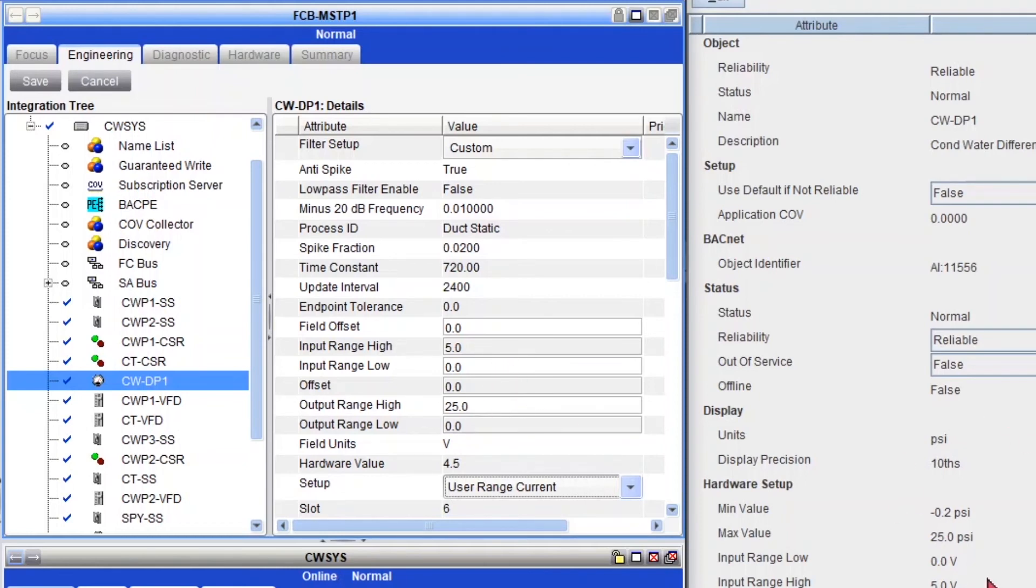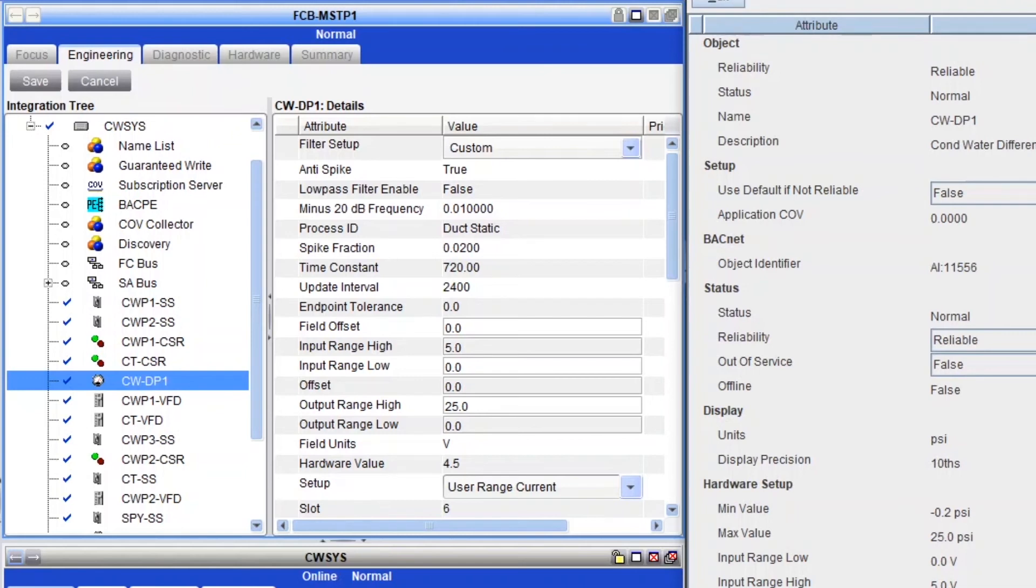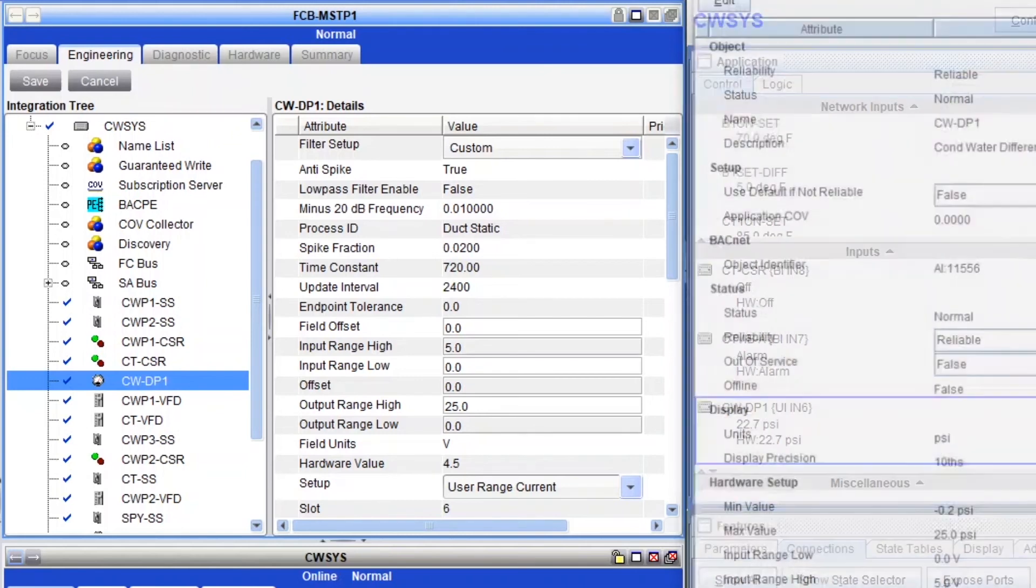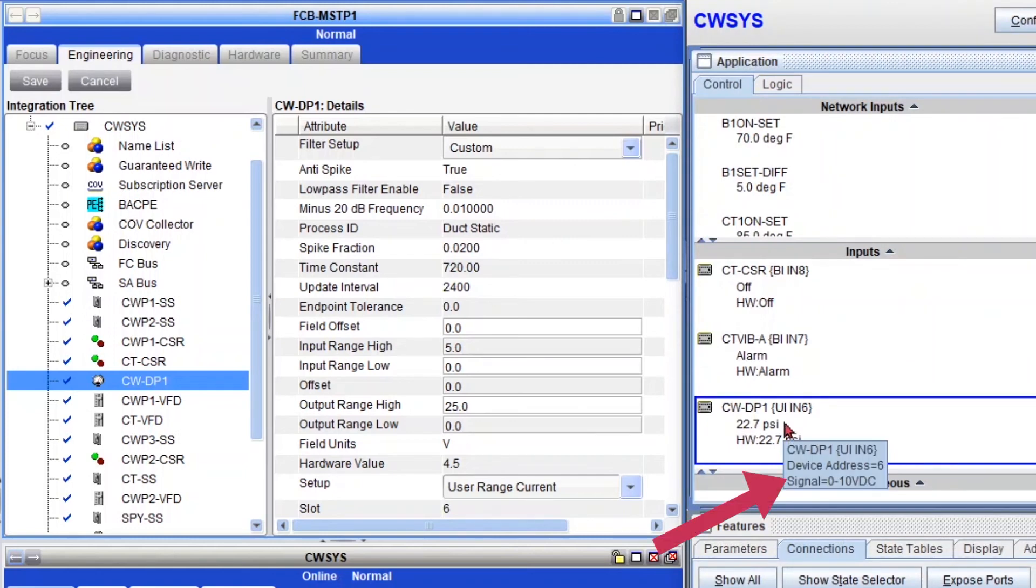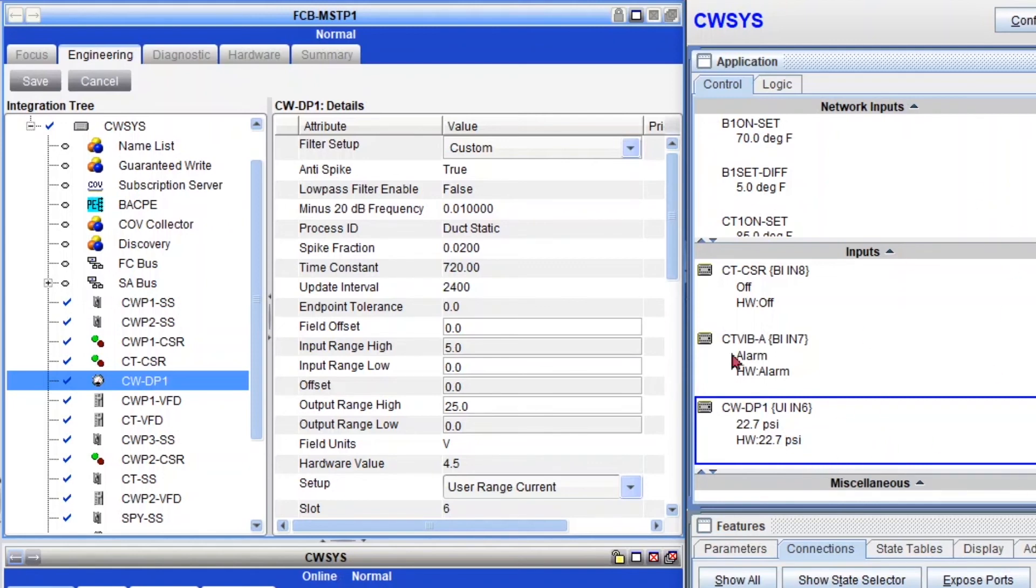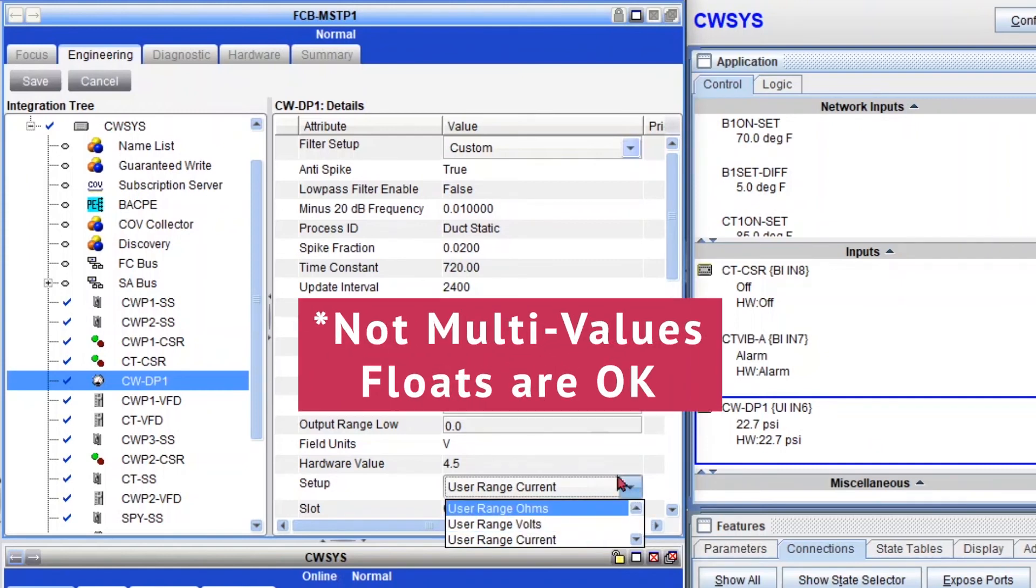But CCT is not going to know that you change the setup of the input. So meaning that it won't know that you change, let's see, let me show you right here. It would still think that it's a signal 0 to 10 volts and not 4 to 20. So even if you upload the application after making the changes, it's not going to take it. So you kind of need to manually change it in CCT. So I do not recommend to change any values like ranges.